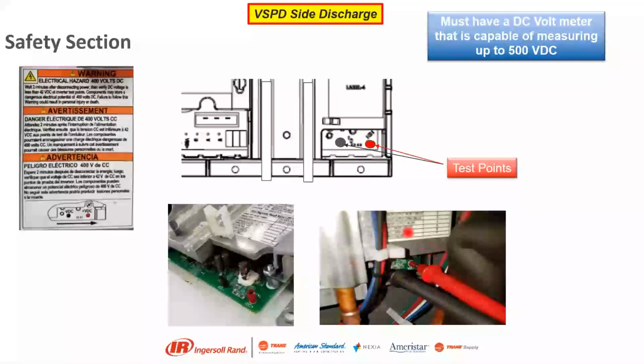If we're diagnosing a drive, I'm going to ask you for our volts DC from the test pins in this location. You can see that a little bit better picture without the probes, but keep that in mind. I always refer your attention down there so I can get a test point of what our voltage DC is, usually right around 333 volts DC to 375 volts DC, normal operation.